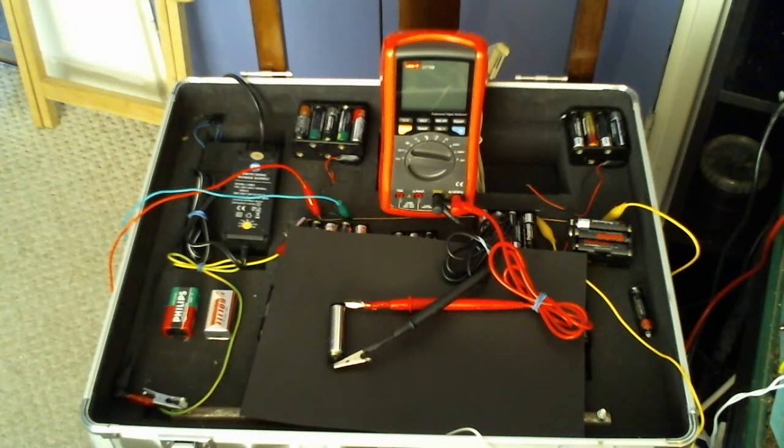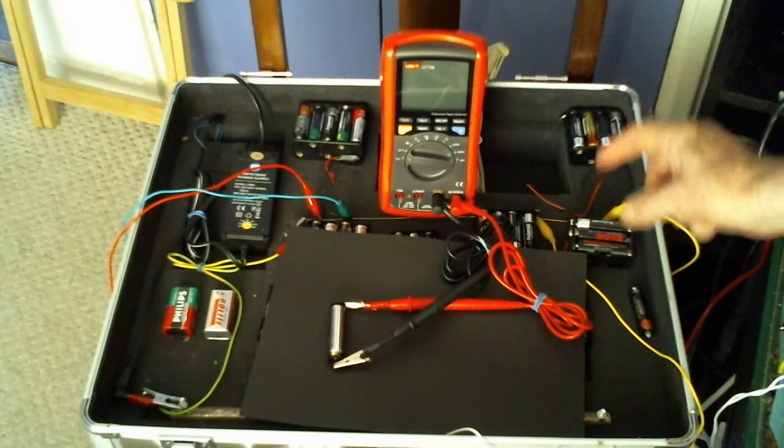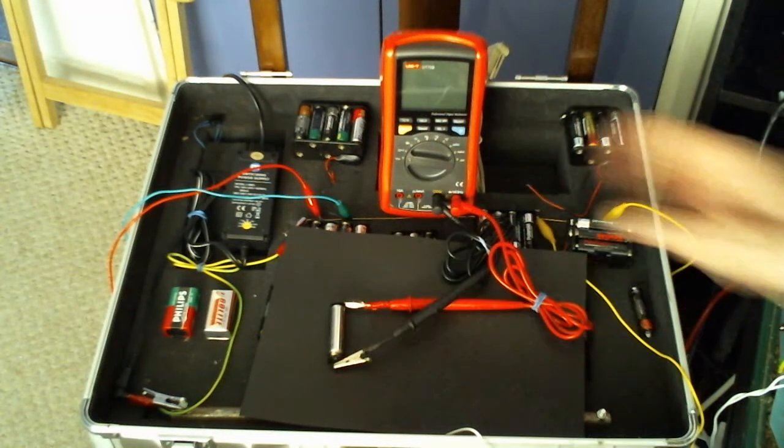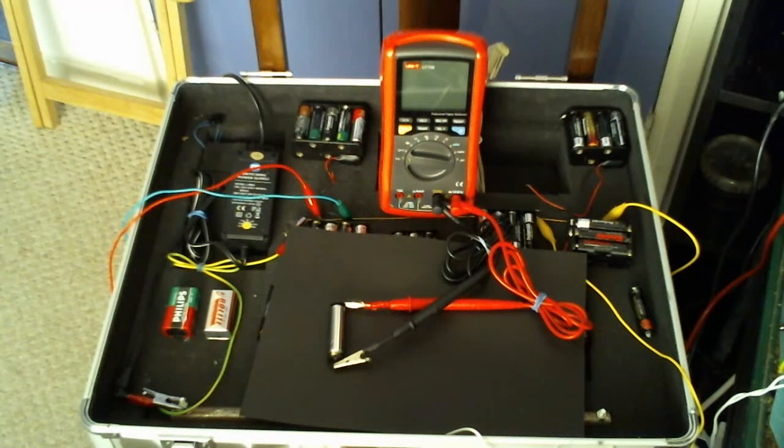It is very important in cathodic protection work to remember that we cannot measure a single potential. We can only measure the difference between two potentials. And that is the reason why it's very important to understand that a corrosion cell consists of two potentials: the potential of the anode and the potential of the cathode.